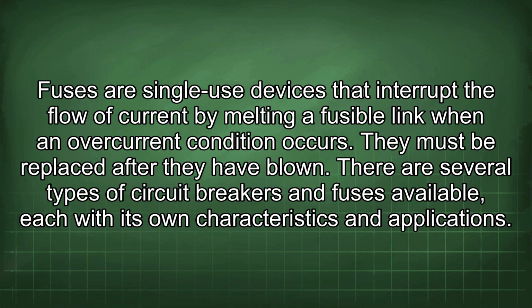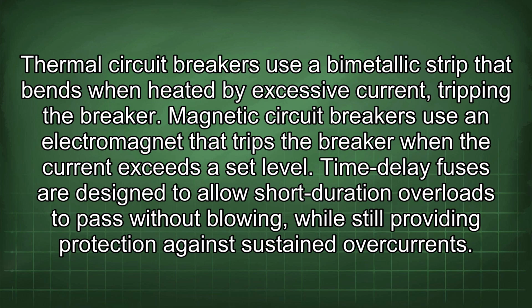They must be replaced after they have blown. There are several types of circuit breakers and fuses available, each with its own characteristics and applications. Thermal circuit breakers use a bimetallic strip that bends when heated by excessive current, tripping the breaker. Magnetic circuit breakers use an electromagnet that trips the breaker when the current exceeds a set level.